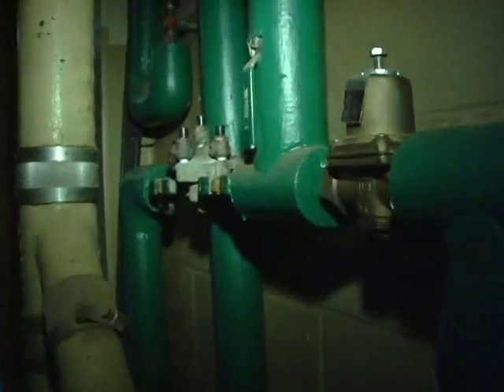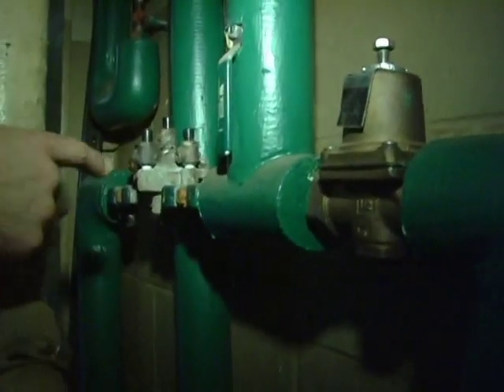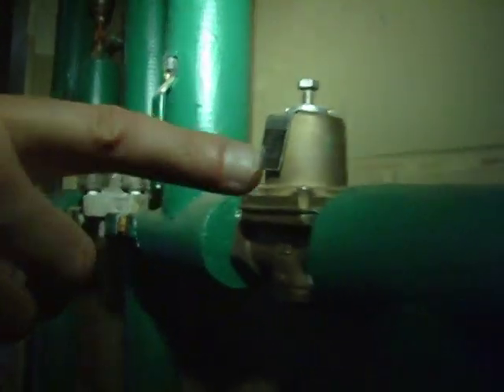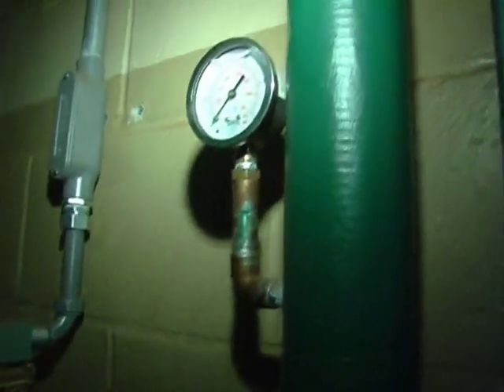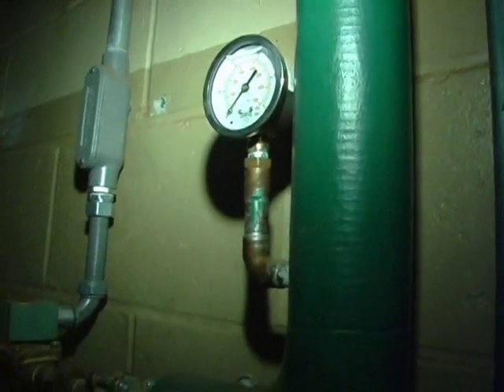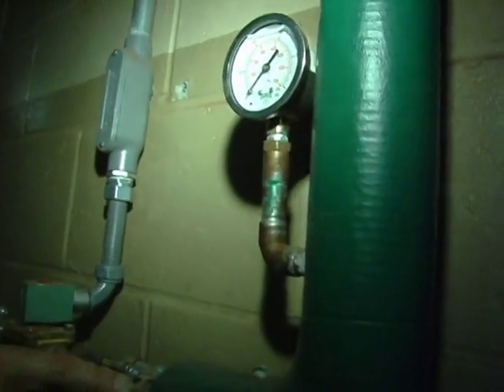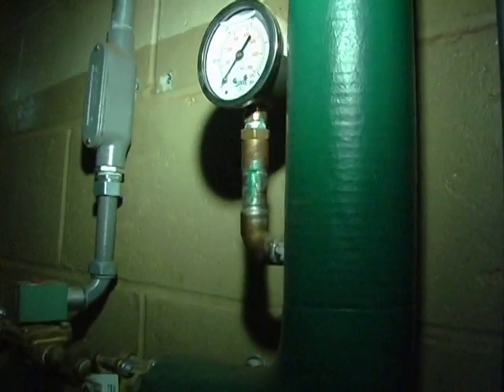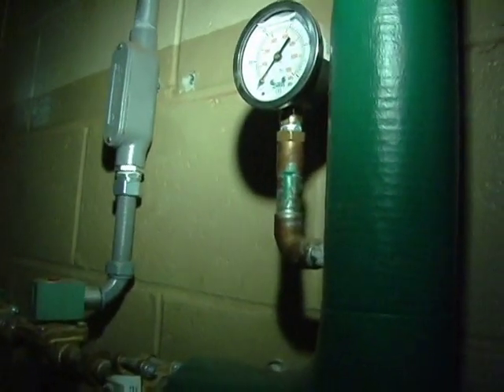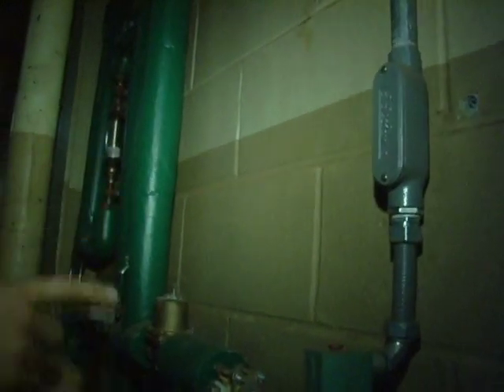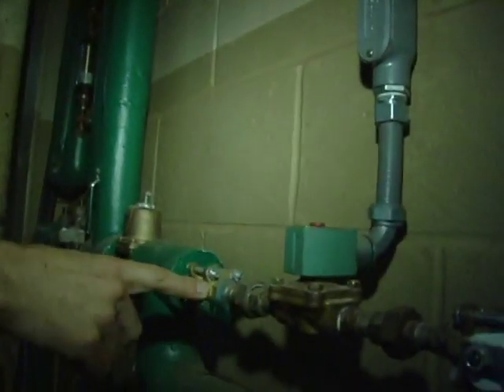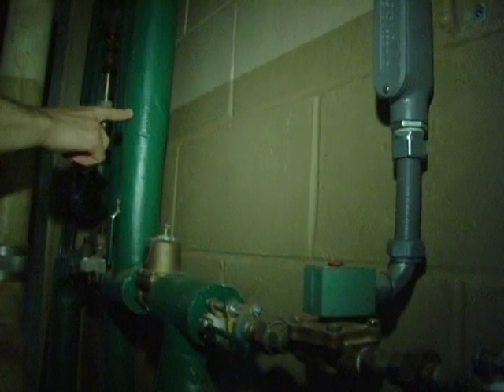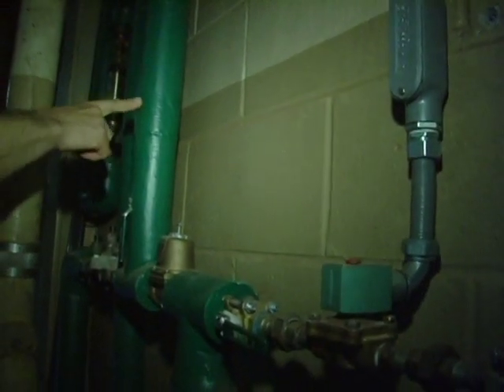This is your plant potable water. You got a backflow preventer, and this potable water is used in two places. It's used on the jacket for the FGR fan for cooling, and it's also used in the fogging nozzles. This has gotta be the mist line here. Oh, this one is the mist line. I'd say so, because this one's a solenoid for the FGR fan. Okay. Yeah. This one here goes to the fogging nozzles. Right. Yeah, fogging nozzle.